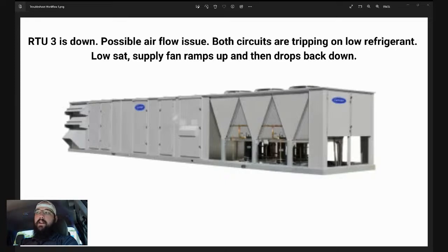Now, how do we find out what the logic is supposed to be doing? So the question is, what could cause our supply fan to drop out every time a compressor tries to engage, and then when the compressor shuts back down, our supply fan comes back on? We'll stick with this application on a large Carrier RTU as an example. What are some possible things? Where would you start with that kind of troubleshoot?